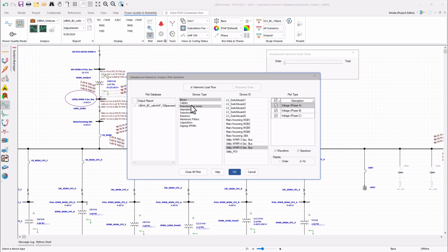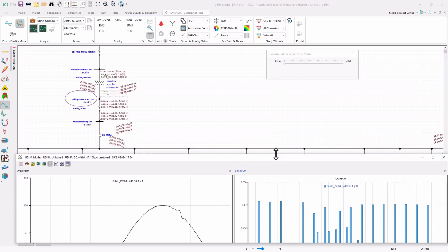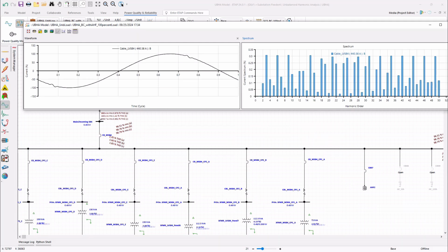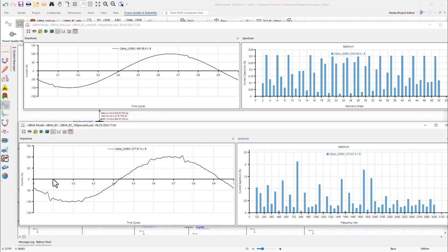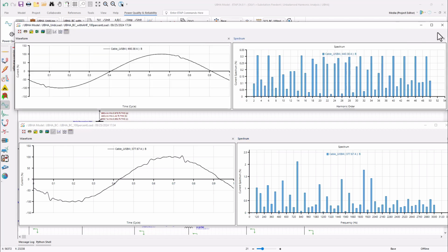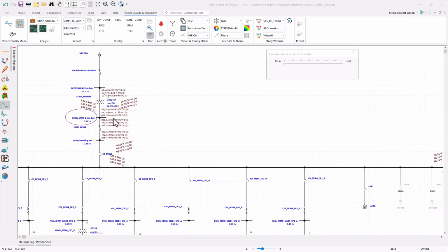So let us generate this plot for this cable LVSB4, and let's compare it with the case where we had distortion before. That is the case with 100% load and no filter installed. So the waveform got cleaned significantly with the active harmonic filter in place. So as part of this harmonic evaluation, we noticed violations of percentage total current harmonic distortions at this PCC location. To address the issue, we have run scenarios that were set up with active harmonic filter or with passive harmonic filter installations in the location. In both cases, we've noticed significantly reduced distortion in the waveform.